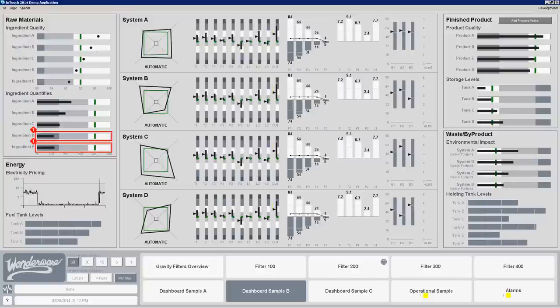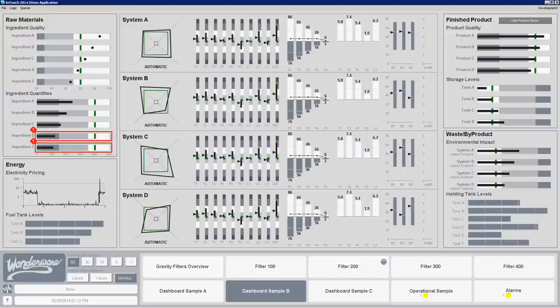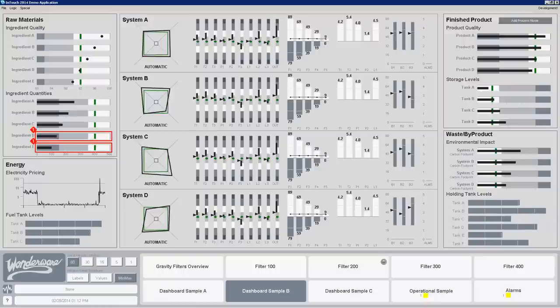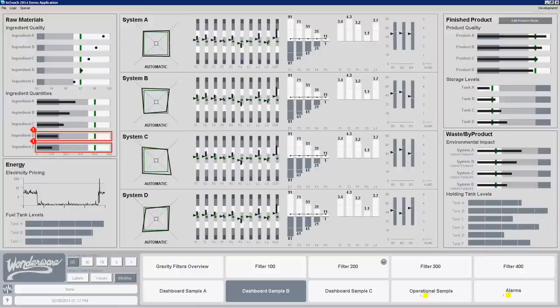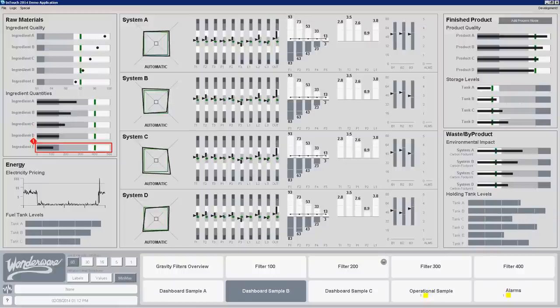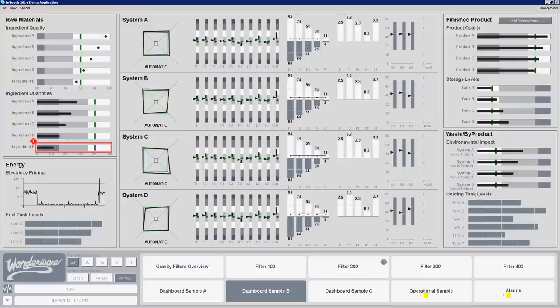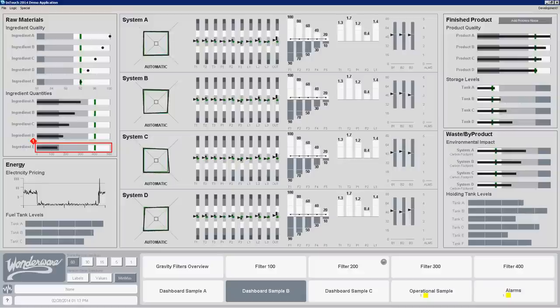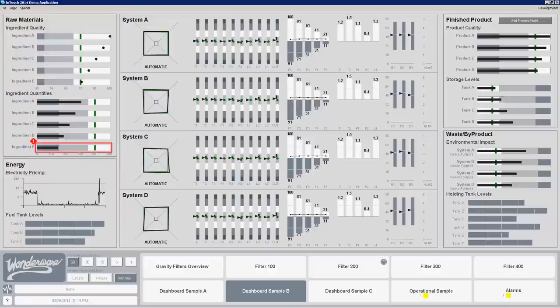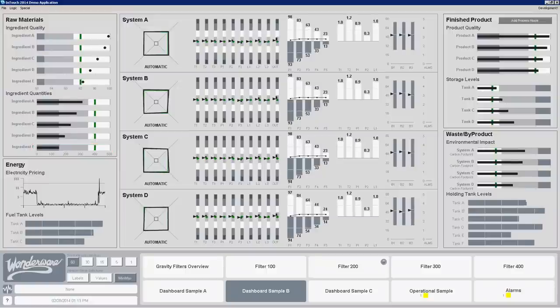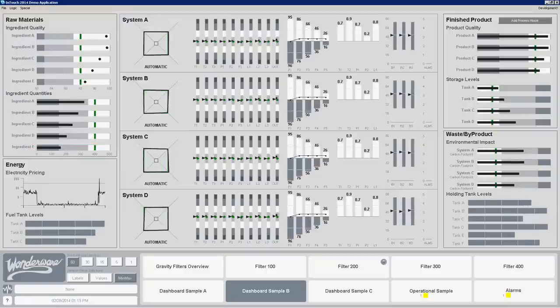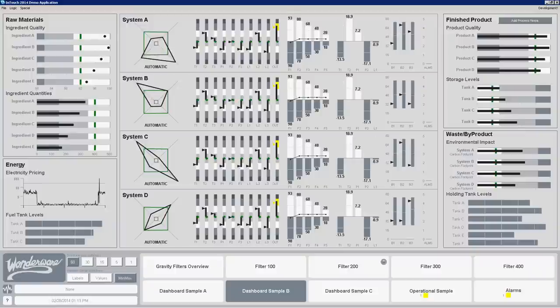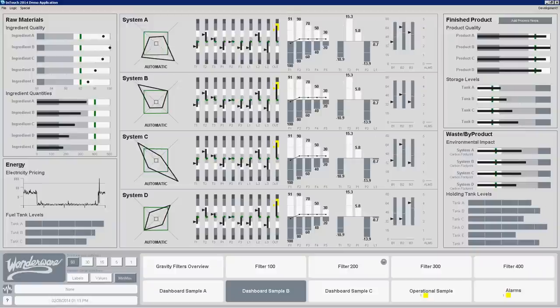So really what you need to do is you need to have a way of effectively rolling up potentially thousands of data points into just those that are going to be the key performance indicators that identify for an operator that something may not be right or an action may need to be taken. This isn't necessarily for alarms, there are other tools for alarms, but really if they're trying to understand from the process how well is the process performing.